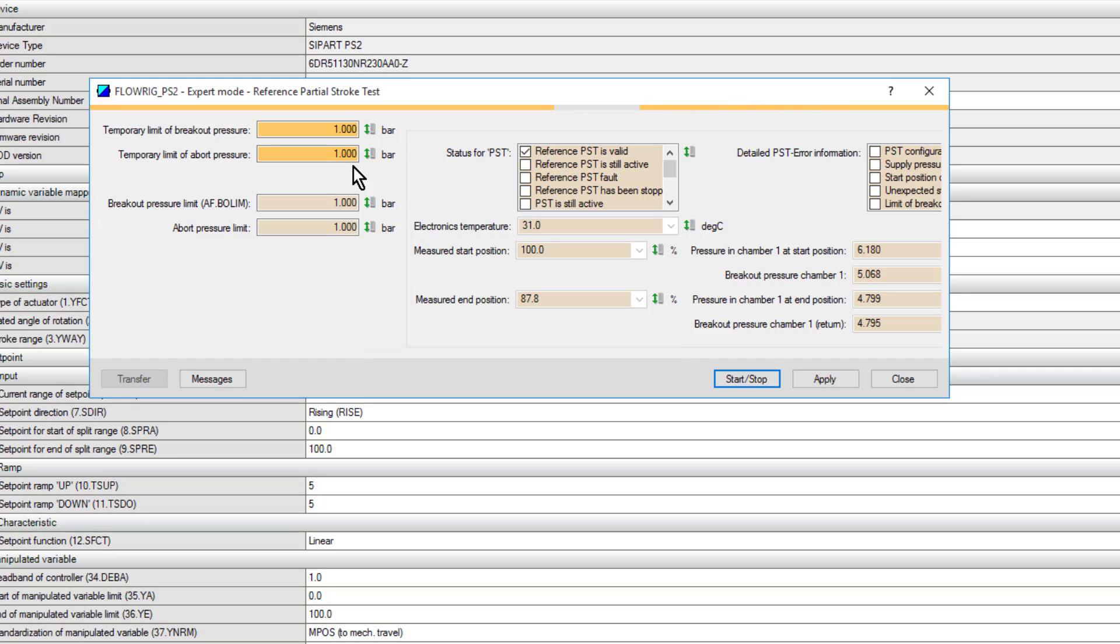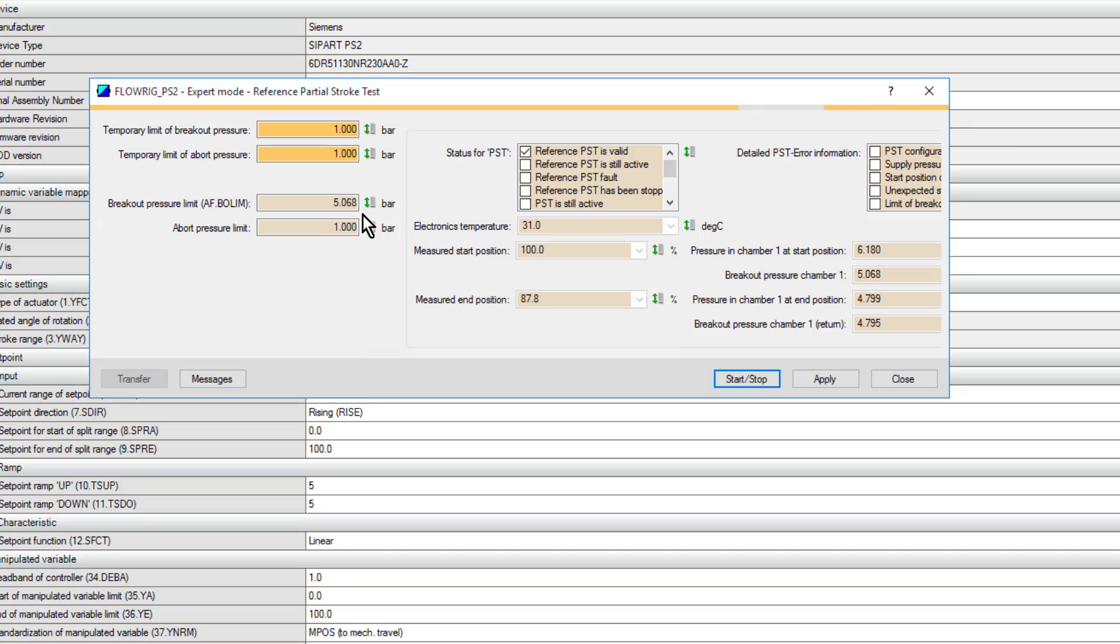My valve is that inconsistent and it is a diaphragm valve that is heavily reliant on the pressure inside the pipe. So I just lower both of these to 1. The lower the value, the more you're letting it drop the pressure to allow it to move. I've lowered those to 1, clicked on apply, and then we're going to start our test.